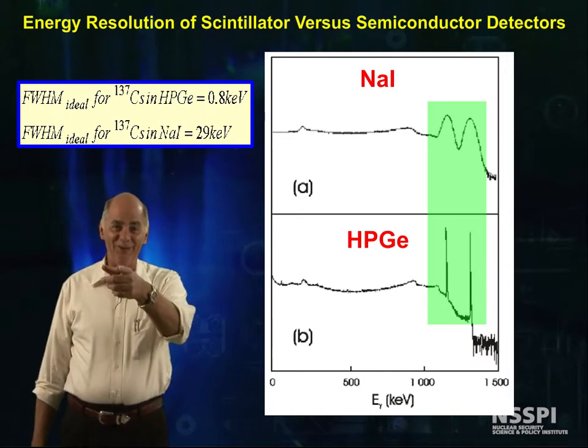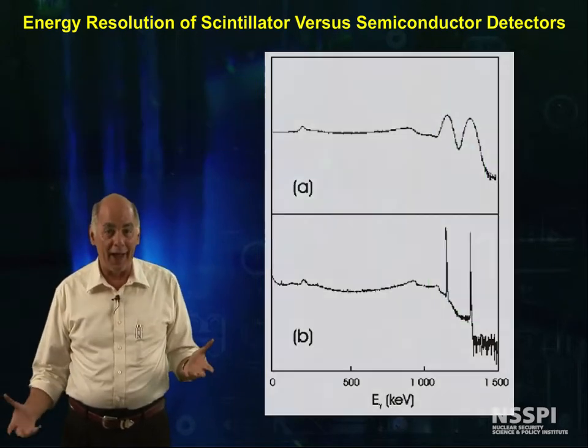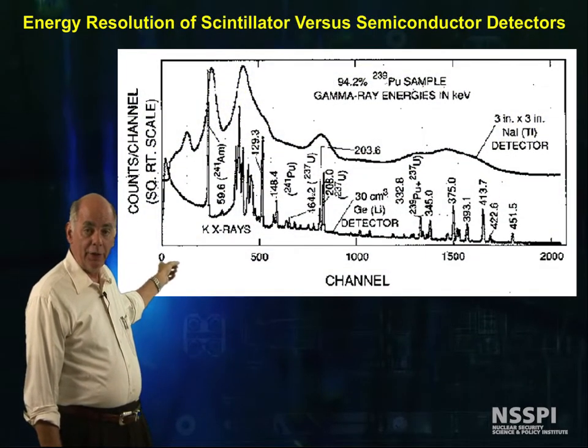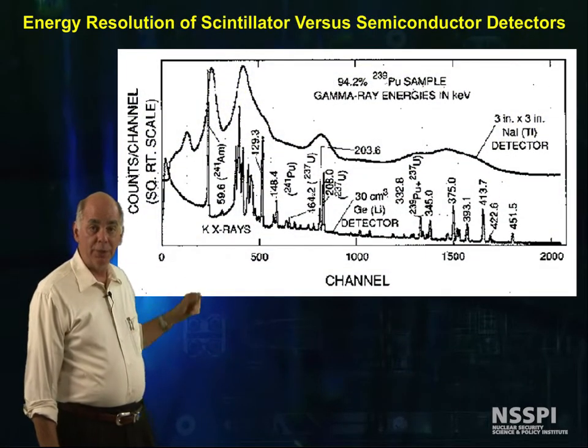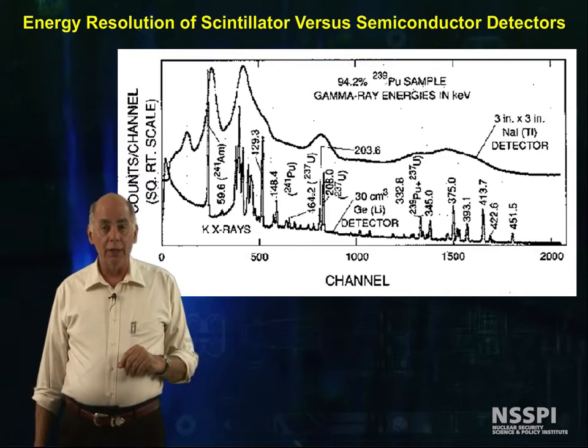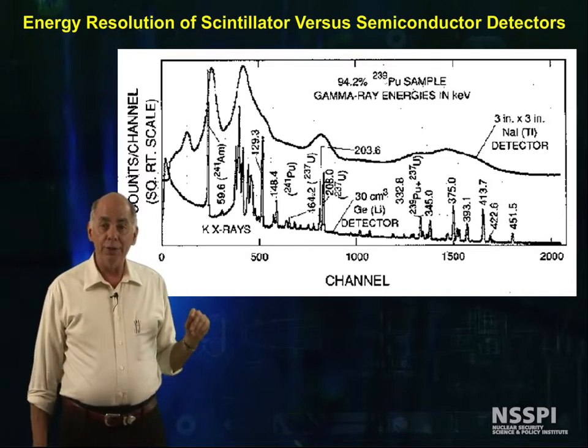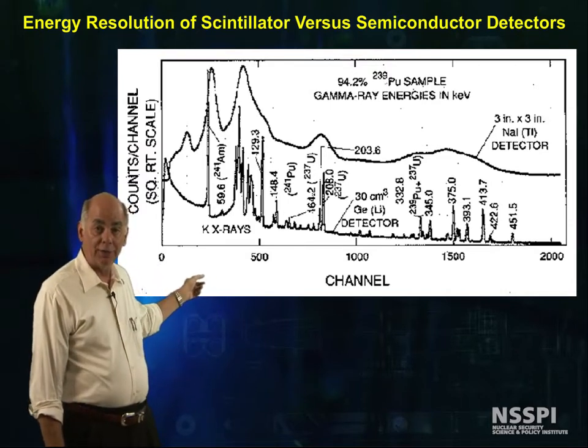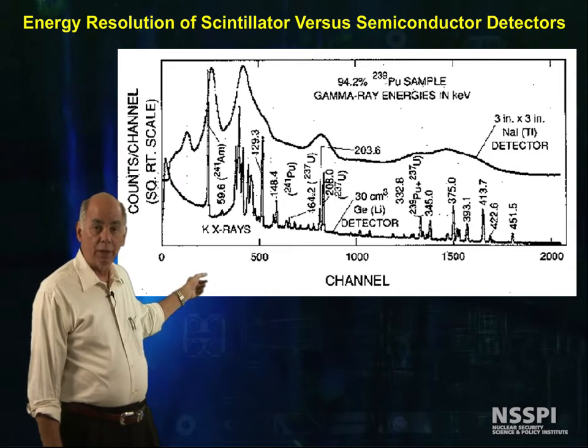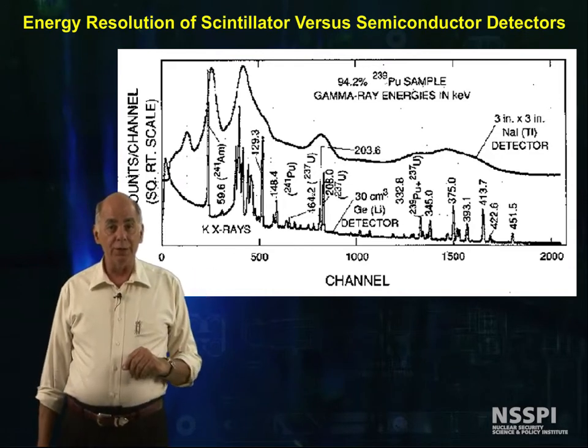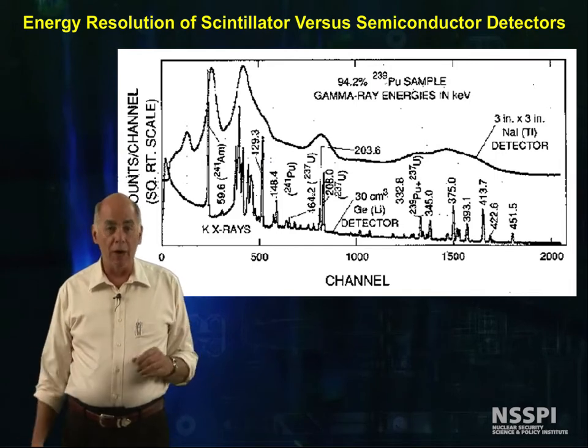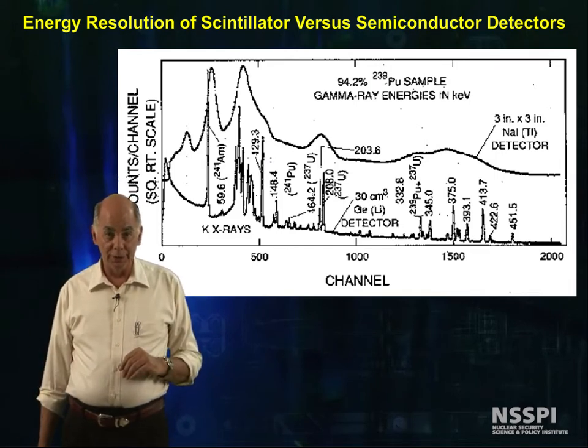This is why we pay the money. What sodium iodide smears out beyond recognition, high purity germanium resolves into individual peaks. We can go and identify minor constituents in a material that we can only dream of when using scintillators.